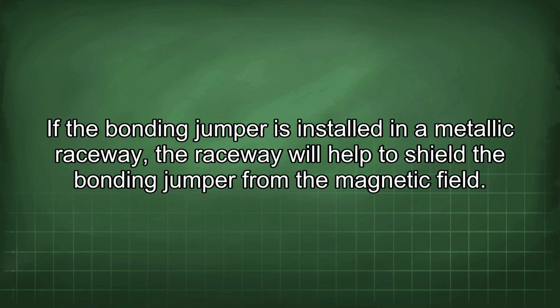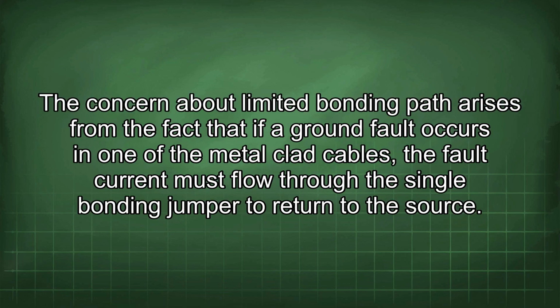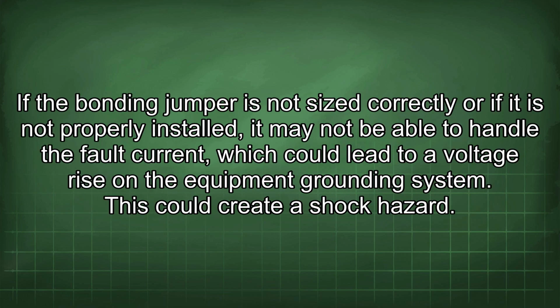the magnetic field. The concern about limited bonding path arises from the fact that if a ground fault occurs in one of the metal-clad cables, the fault current must flow through the single bonding jumper to return to the source. If the bonding jumper is not sized correctly, or if it is not properly installed, it may not be able to handle the fault current, which could lead to a voltage rise on the equipment grounding system. This could create a shock hazard.